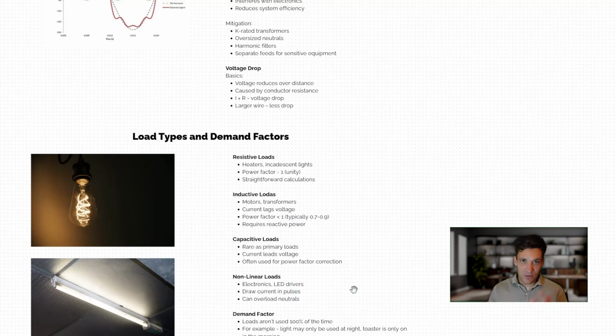The final thing is, and this is very intuitive, that not all loads are going to be used 100% of the time. So demand factor is an adjustment of the load based on how often it's going to be used. For example, your lighting in your house, you might only use it during the night, but it's not going to be used during the day. So that might have a demand factor of something like 50%, or your toaster, you might only use for 2 minutes a day. So if you're sizing a system, you wouldn't size it assuming the toaster is always on because you're going to drastically oversize the system. So demand factors are standard applications we apply to different types of loads to adjust them for how much they're likely going to be used.